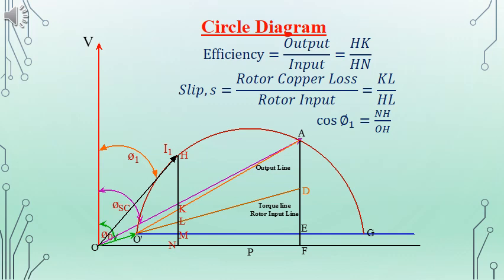To find the efficiency, we take the ratio of HK to HN, where HK corresponds to the output and HN corresponds to the input. The portion above the output line, HK, is the output, and the entire vertical length HN is the total input. To find the slip S, recall that rotor copper loss equals S times the air gap power, or S times the rotor input. From this, slip S can be calculated. The power factor cos phi1 equals NH divided by OH, which is the same as I1 cos phi divided by I1.